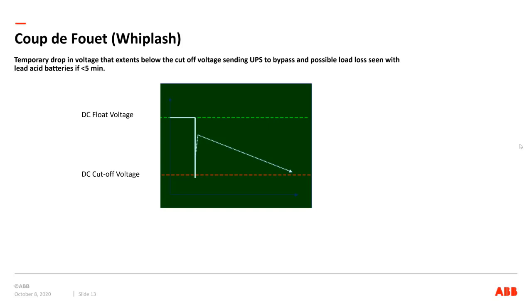So with pure lead, and probably the main reason we are seeing people starting to look at them, even if they are a little bit more expensive, is that we can now size a battery all the way down to 2 minutes, where a traditional VLA cannot go below 5 minutes before running into potential issues with coup de fouet.